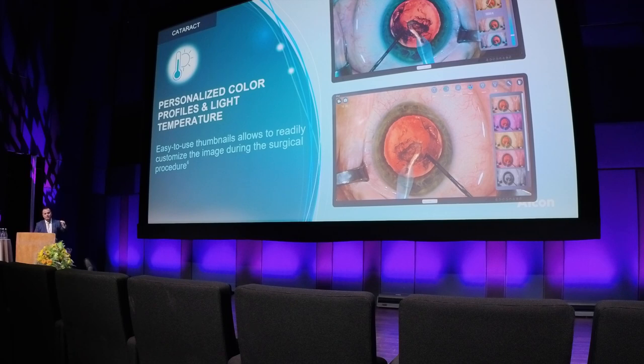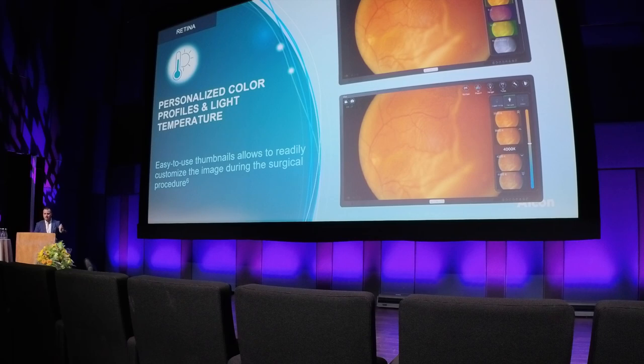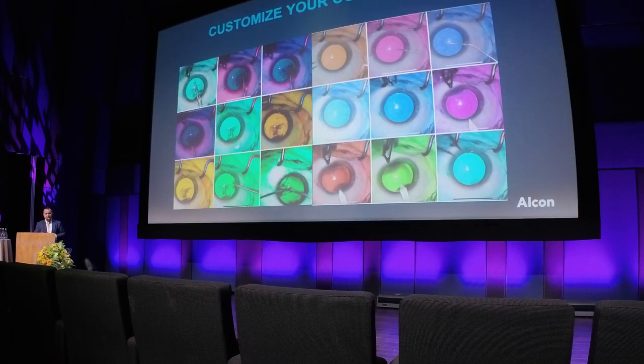Here are examples of personalized color profiles. You can tailor the color temperature or use the white balance in order to have the best possible image for your own color perception. With software version 1.431, you have the option to use different filters — monoscopic, red-free, monochrome, blue — and you can also create your own filters. You have the freedom and ability to manipulate the image to highlight structures of interest.